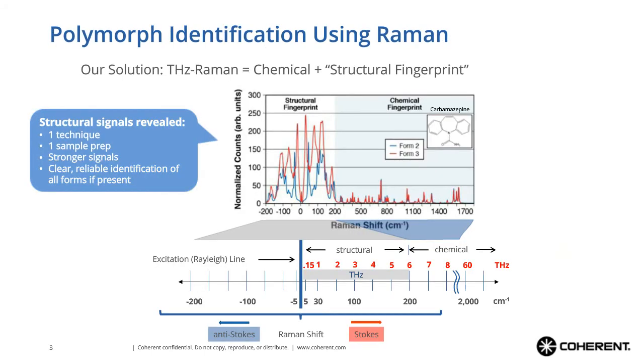One of the key advantages of low-frequency Raman is the ability to see structural changes in materials. This structural fingerprint below 200 wavenumbers is fundamentally different from what you'd find in a traditional chemical fingerprint region, because you're looking at vibrations of the entire molecule or crystal lattice modes. These bands tend to be much, much stronger than the conventional fingerprint regions — up to 10x stronger.